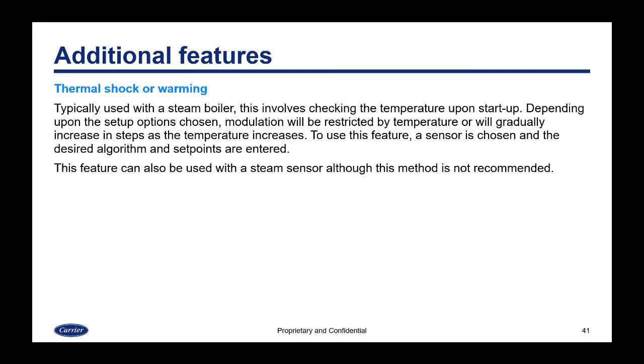We also have thermal shock or warming available as an additional feature. This is typically used with a steam boiler, and this involves checking the temperature upon startup. Depending upon the setup options chosen, modulation will be restricted by the temperature or will gradually increase in steps as the temperature increases. To use this feature, a sensor is chosen and the desired algorithm and set points are entered.